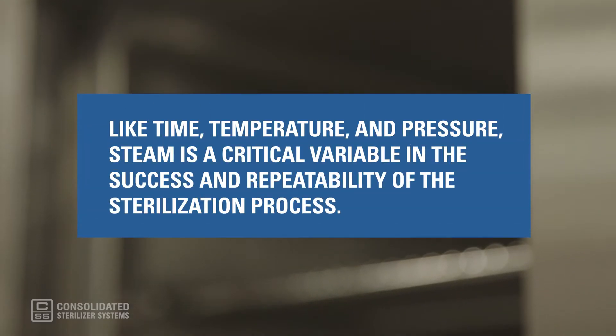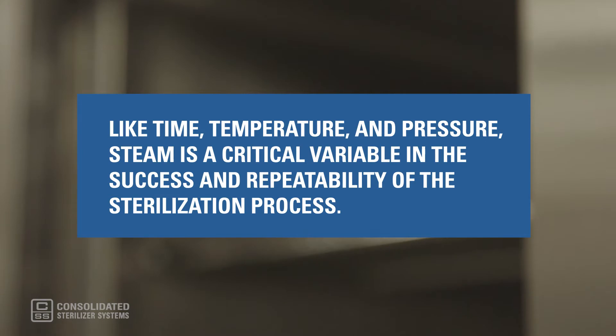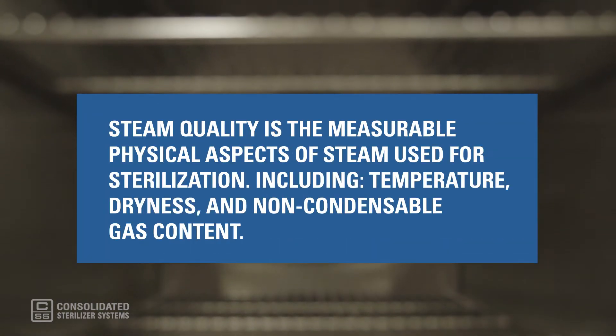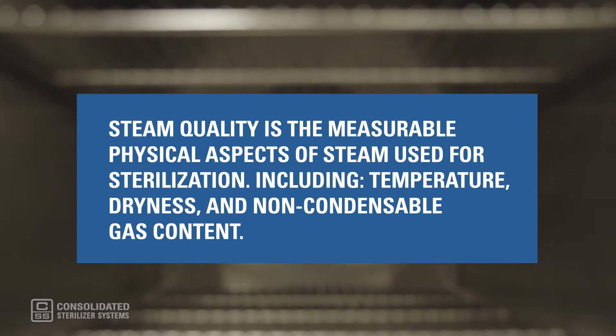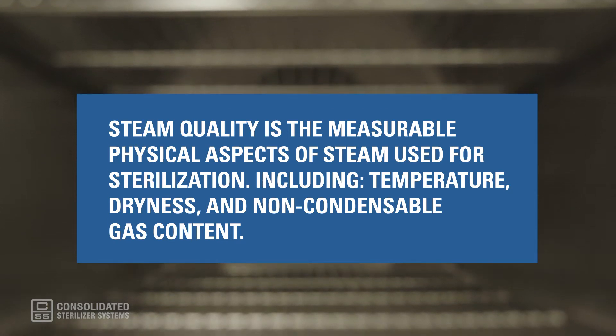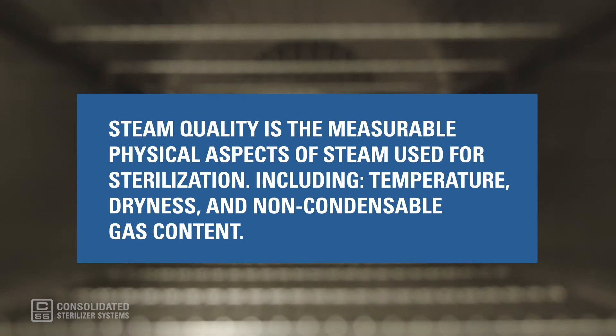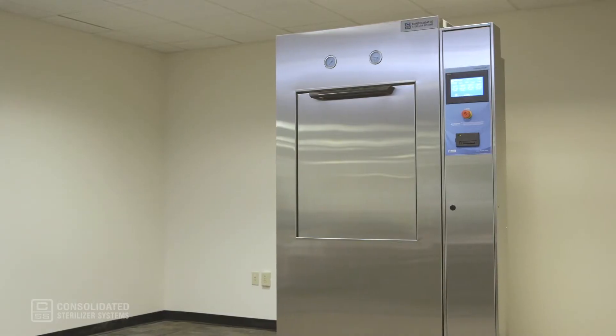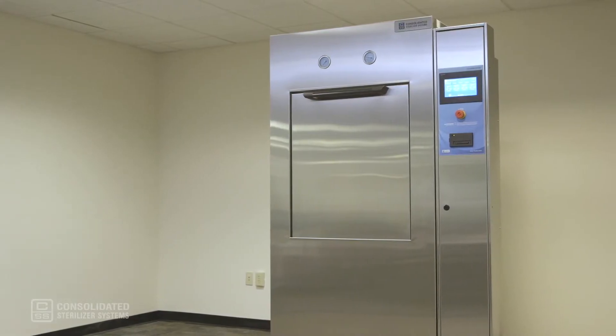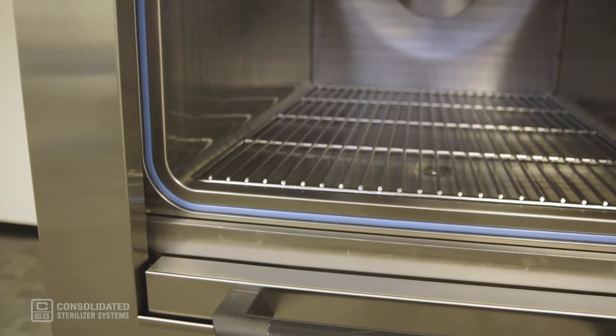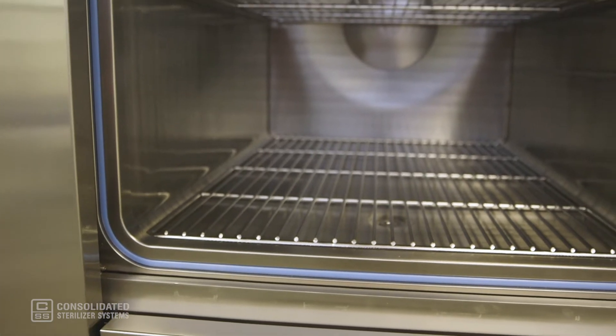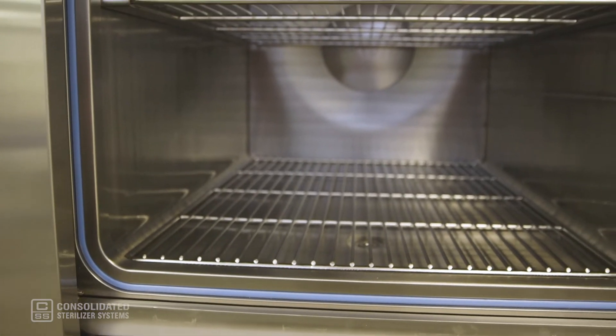Let's first discuss the importance of steam quality. Like time, temperature, and pressure, steam is a critical variable in the success and repeatability of the sterilization process. Steam quality is the measurable physical aspects of steam used for sterilization. These include temperature, dryness, and non-condensable gas content. Deviations from established ranges of these aspects can result in sterilization indicator failures, staining, and corrosion of instruments and containers.